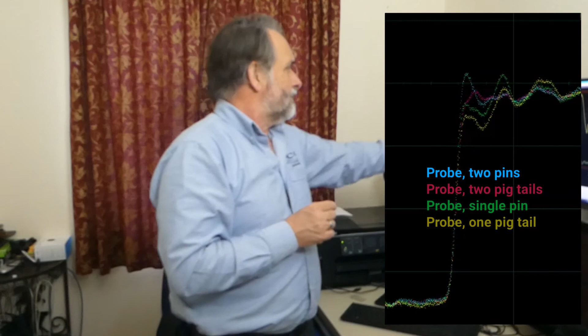Well, we take the compromise. We take the waveform or the bandwidth compromise, and it's a bit similar with these probes, but at much higher frequency. Really, we should use both grounds. That's ideally. But if we don't, then the response differences that we see here, the overshoot, perhaps a dB and a bit above the flat line. The undershoot here, the worst case, perhaps a dB or so below. You make a small response compromise if you don't use the 2 ground pins.